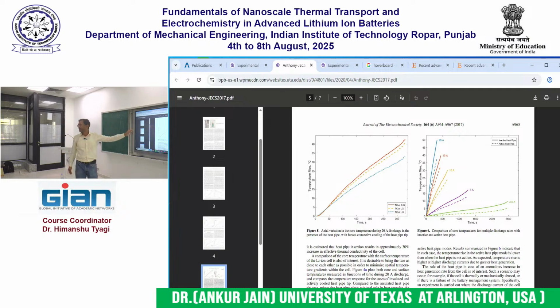One advantage of heat pipe cooling is that it is passive in nature. The heat pipe is just sitting there. You don't have to pump the cooling fluid, the working fluid inside it. All you need to do is blow air outside at the other tip of the heat pipe, which is not very expensive. For that reason, heat pipe cooling is very attractive.